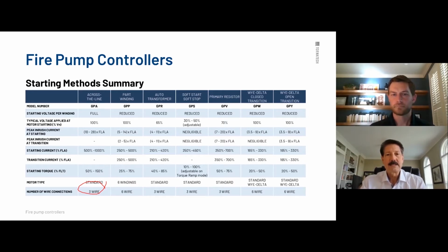Typically, when you get into this type of design, reduced voltage is always trying to reduce the current inrush in an electrical system. High inrushes in an electrical system cause adverse effects. It could actually induce noise and spikes back through the system, which could affect other electronic equipment within. Talk about critical production areas, hospitals, radio stations. Different things where you could have that noise impact on the electrical system itself.